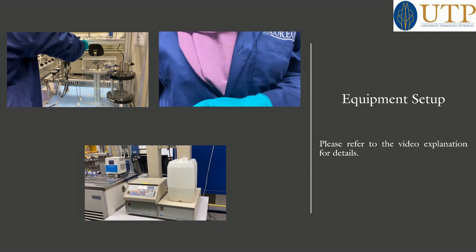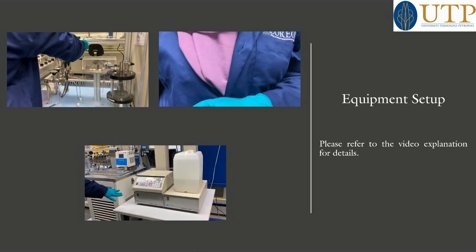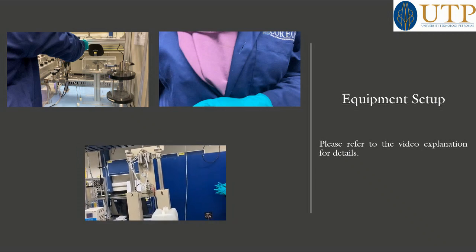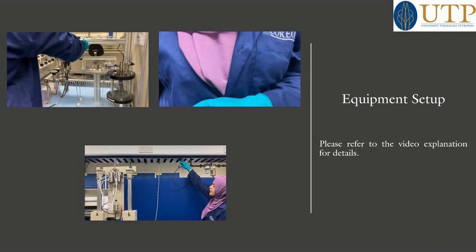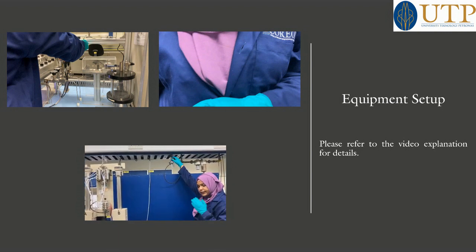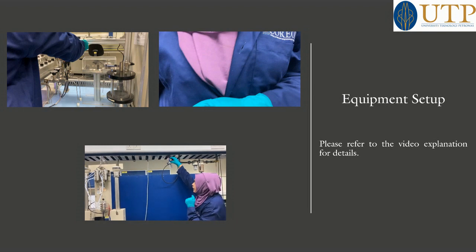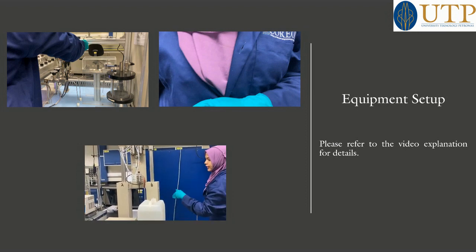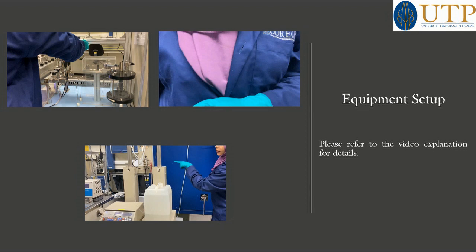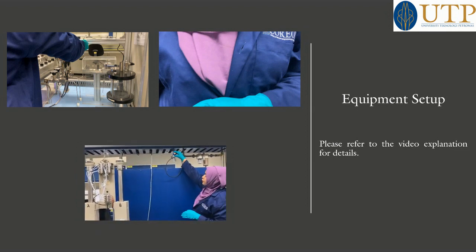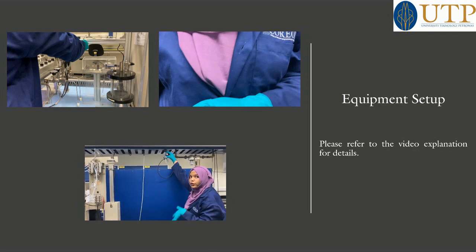So now this is the thing, it's already on, and the main thing for this equipment, this one, there is an air supply. This one should be on every time, because this air is helping to inject the water, to fill and to inject it in my accumulators.